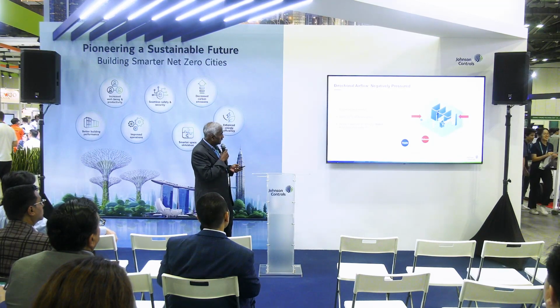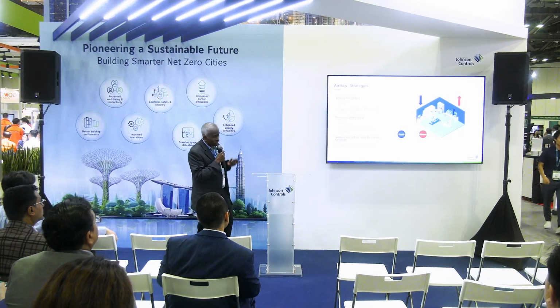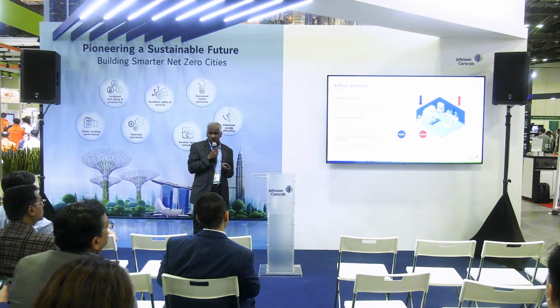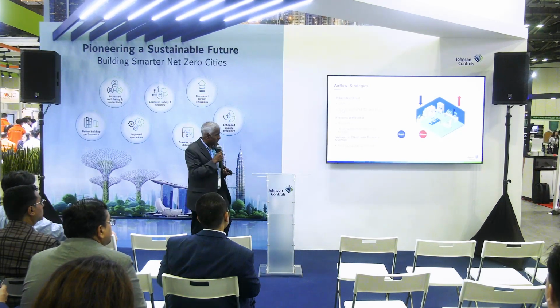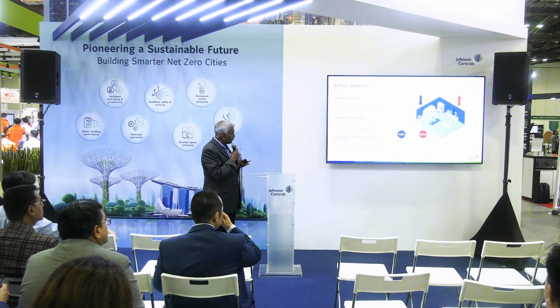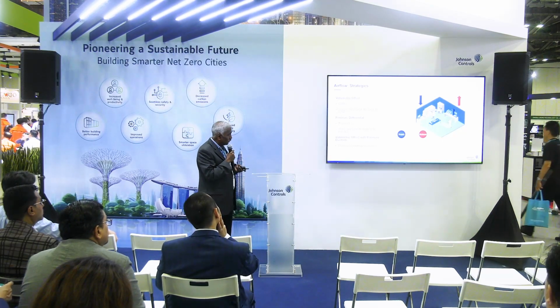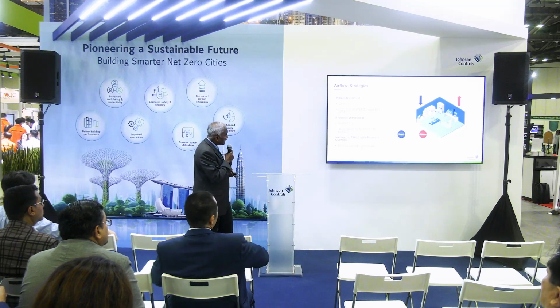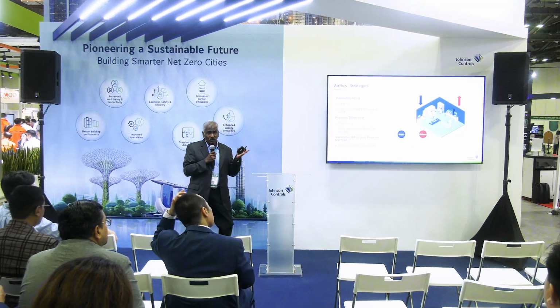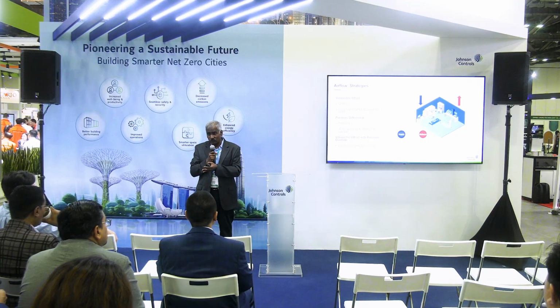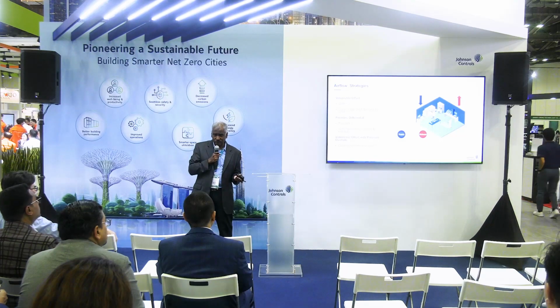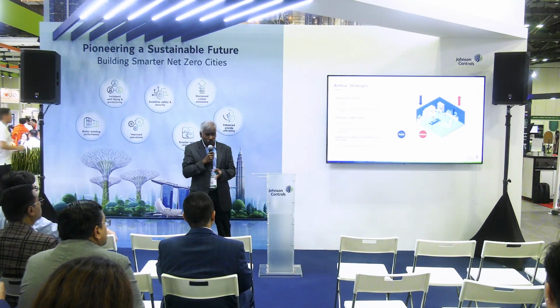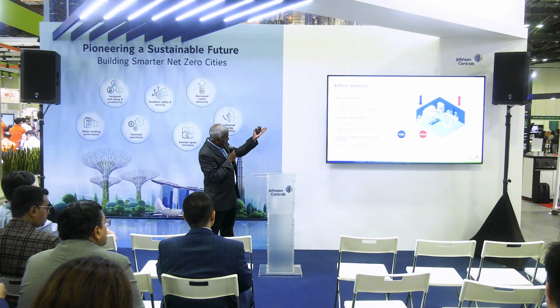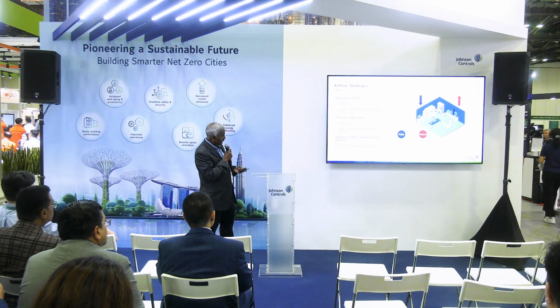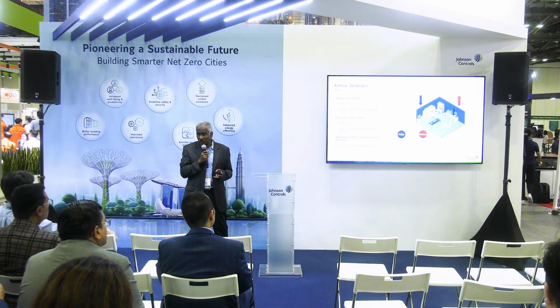These are very fundamental. Then we're going to talk a bit about the strategy, because that ties back to how the Venturi valve solution comes in, right? So there are three control types. The common one is the volumetric offset, basically the CFM differentiation. We talked about supply and exhaust, right? So usually it says 100 CFM or 200 CFM. So that's one control portion of it, all right? For example, the supply is 1000 CFM, and the exhaust is such that the difference is about 100 CFM.